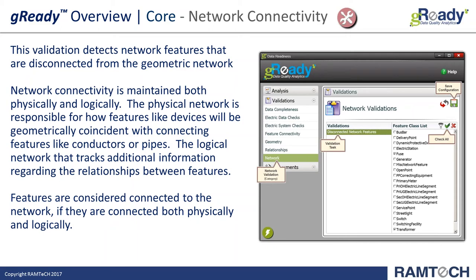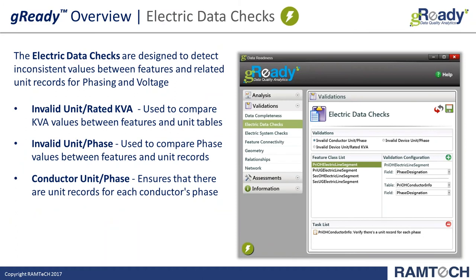We also have our network validation, which looks for disconnected network features. This is different from the disconnected points check — it examines the logical network present behind the scenes of the geometric network. If a device is snapped and part of the network but someone used the disconnect button and never reconnected it, the feature would still be coincident to the line it's snapped to, but as far as the logical network goes it is disconnected. We are able to detect and report on those instances as well. All of these contribute to ensuring your data is connected and as clean as possible when making the jump from the geometric network to the utility network.